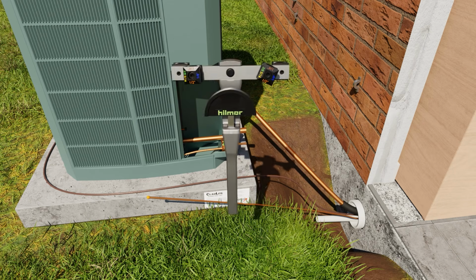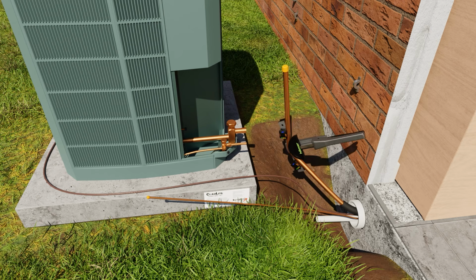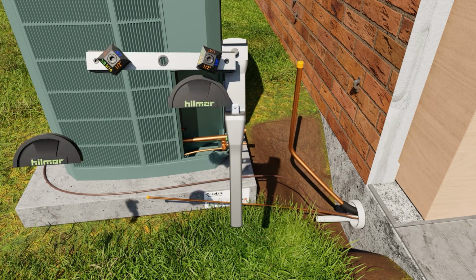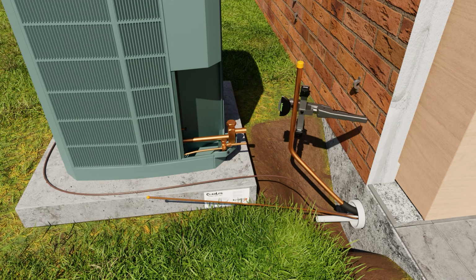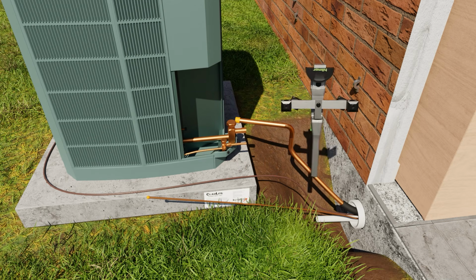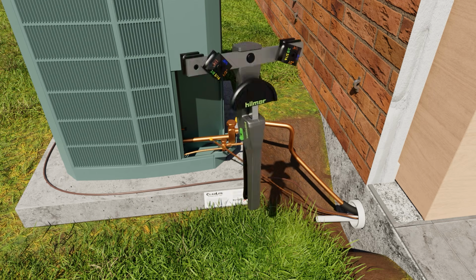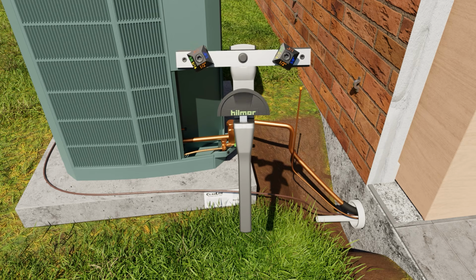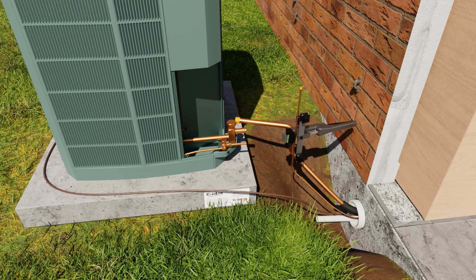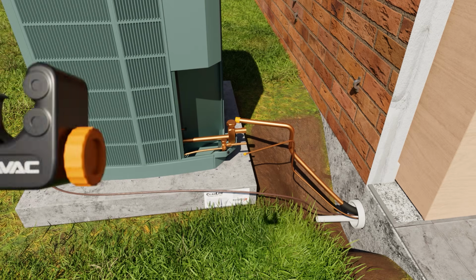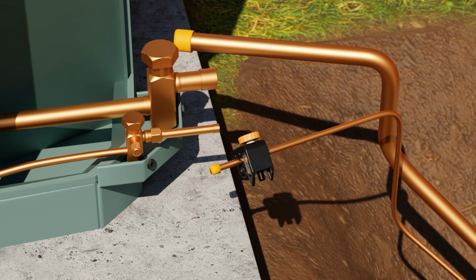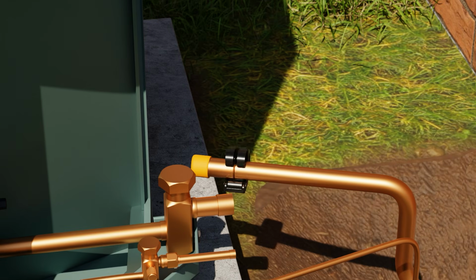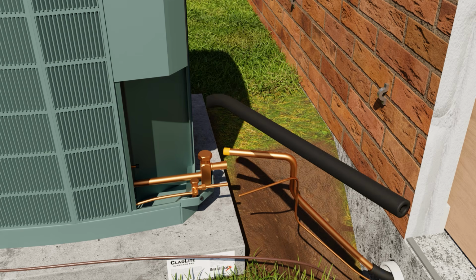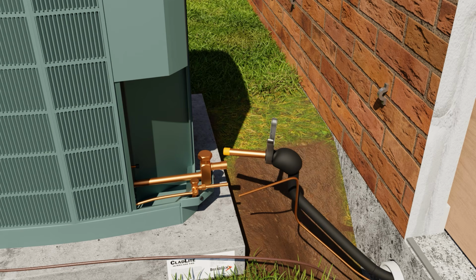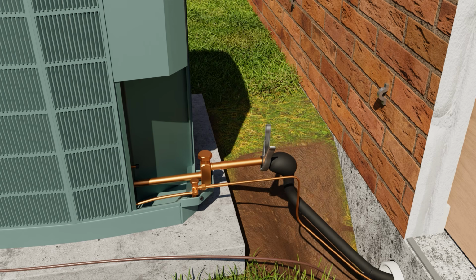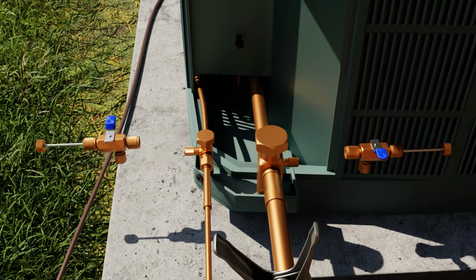Next, we're going to use the tubing bender in both the inward bend and the outward bend. We're showing how to use the adapters in order to bend the tubing in the opposite direction. We do the same with the liquid line. Now we cut the tubing to fit, making sure you leave plenty of excess. At this point, you're going to pull the Schrader cores out of the new system.